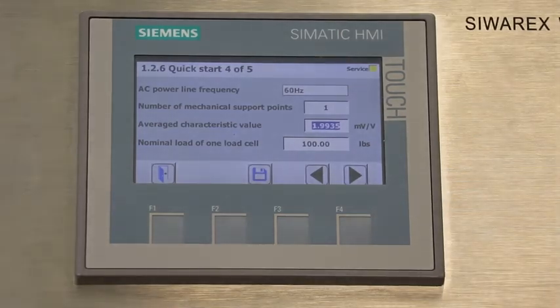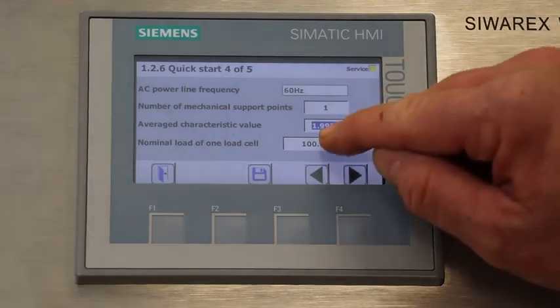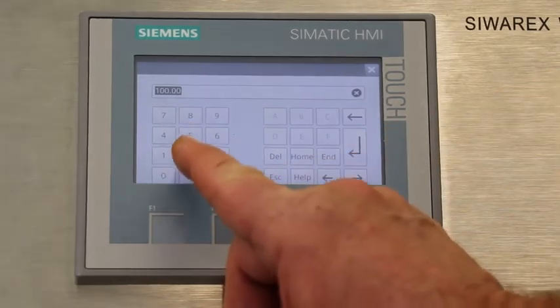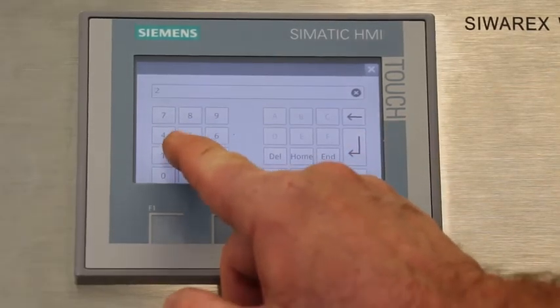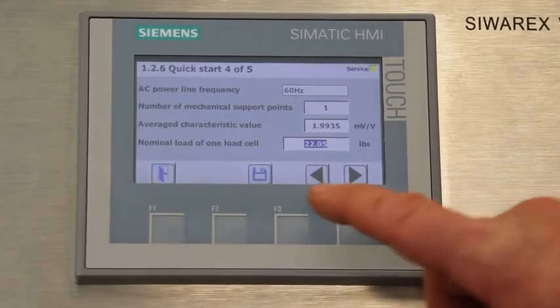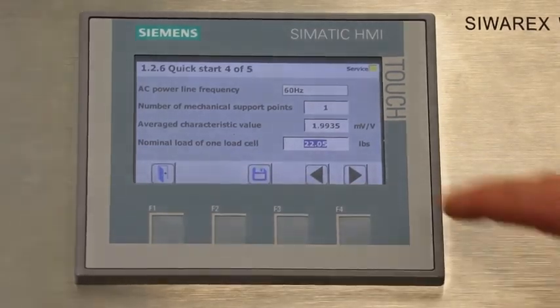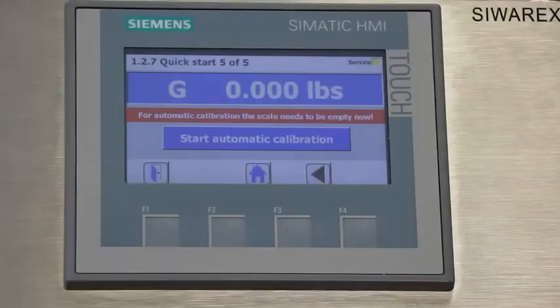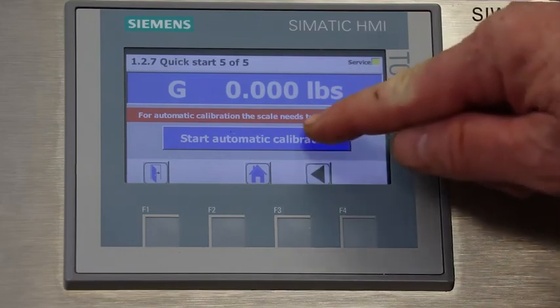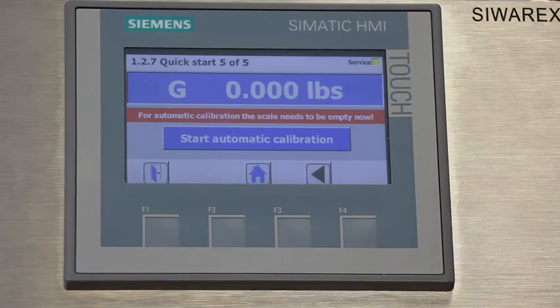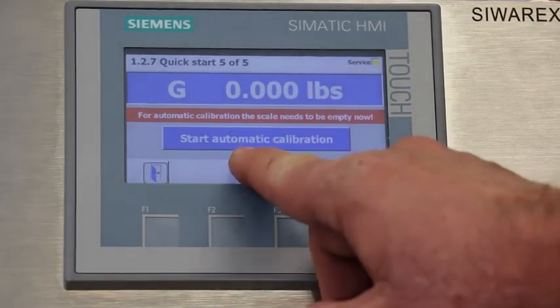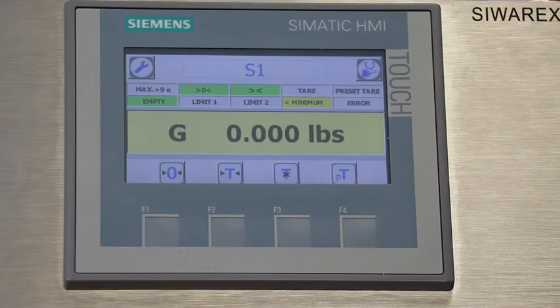And then the last field is the capacity of the load cell. This is a 10 kilogram load cell, which converts to 22.05 pounds. So we'll enter 22.05. We'll save these parameters and advance to the next screen. So now we're back at the calibration screen. This time the calibration screen will only ask you to set the 0 calibration, so we'll do that. Now we'll go back to the home screen, and you can see that the unit is calibrated.